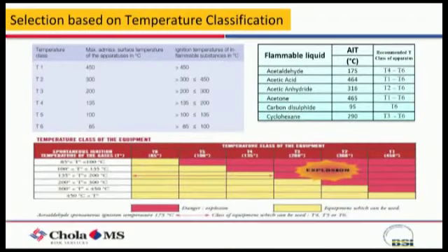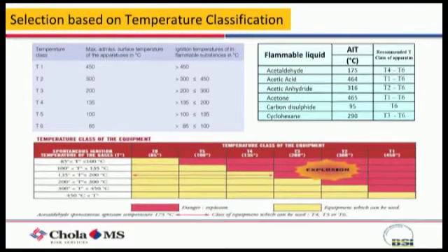So if my auto ignition temperature is say, like acetaldehyde, we were seeing that 175 is my auto ignition temperature. In this area, if I go and put some T3 or T2 motor, I told that T2 and T3 can go up to 200 and 300 degrees, whereas my product auto ignition temperature is 175. So it might immediately catch fire when there is some spillage or anything. So this is how you rate AIT with the T classification.